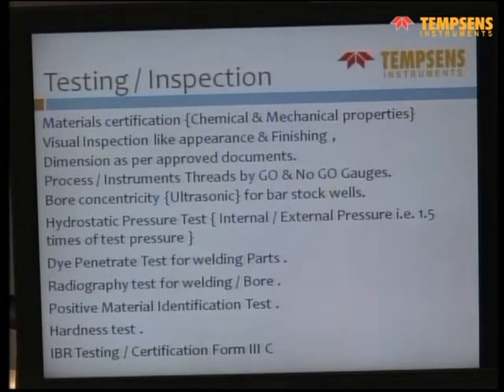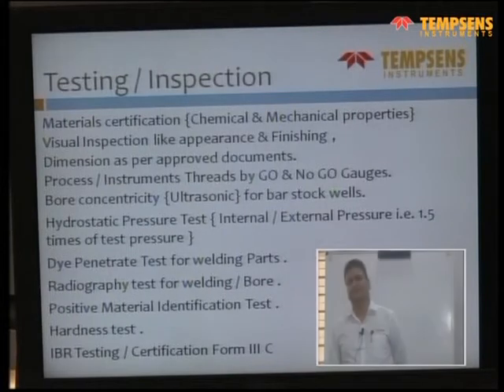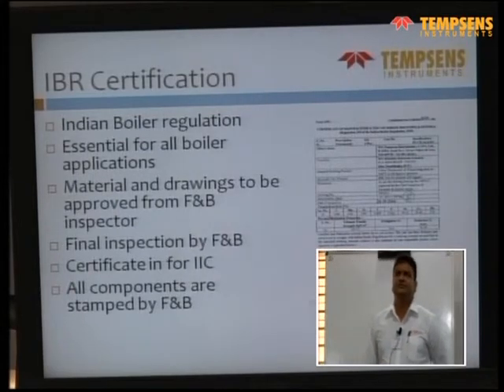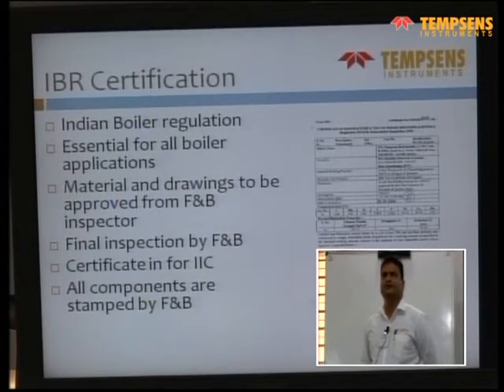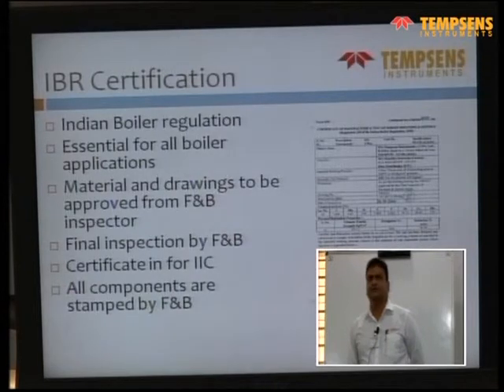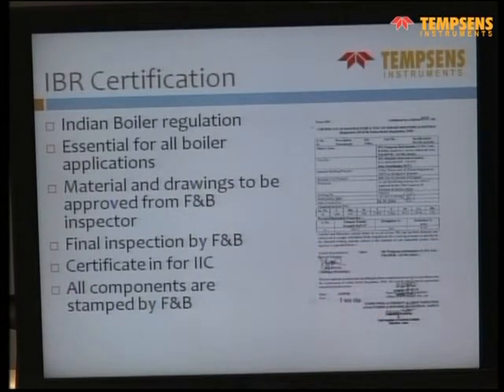Normally it is recommended to do 50% more than the process pressure. DPT test for the welding points, radiography test for the welding points or the bores, PMI for the identification of the material, hardness test, and IBR testing and certification for the boilers. So this is just a simple certificate for the IBR. The material has to be approved, then the drawing has to be approved, and then the final inspection by the boiler inspector is there to stamp the goods.